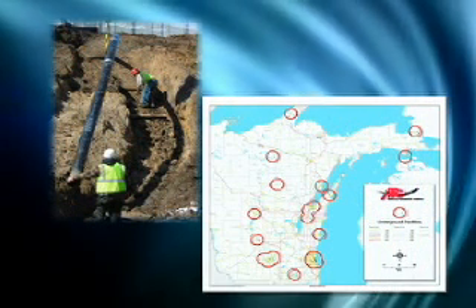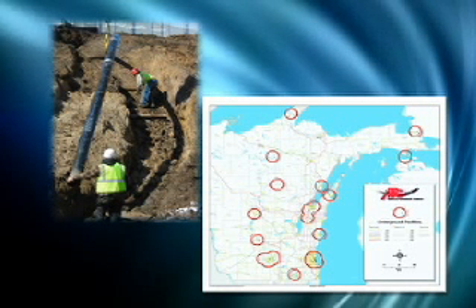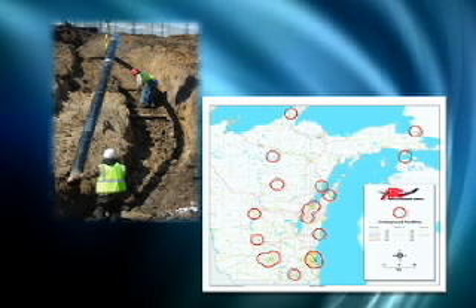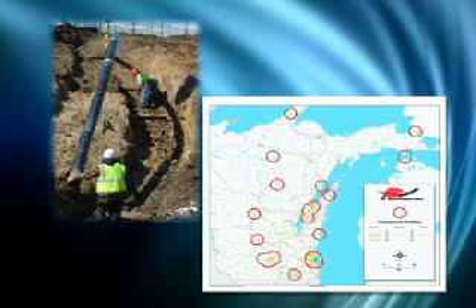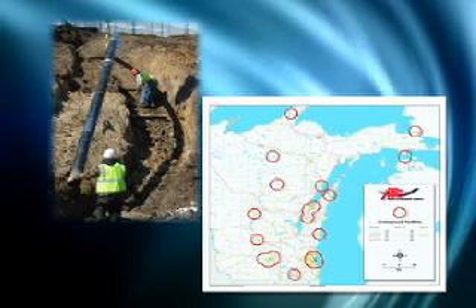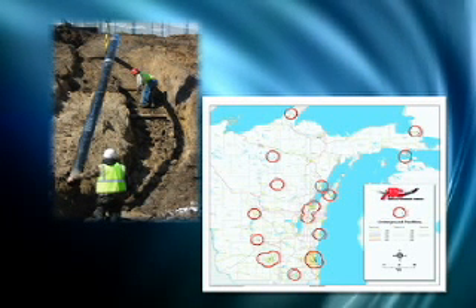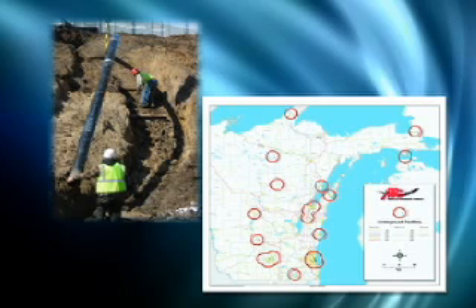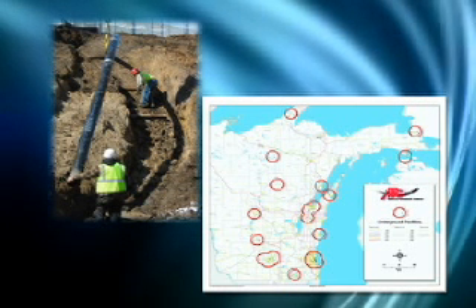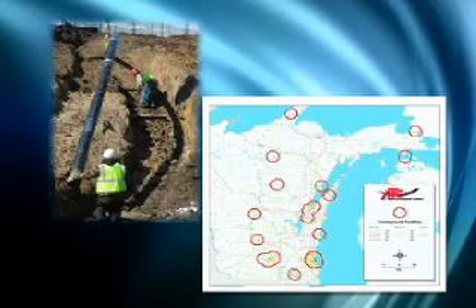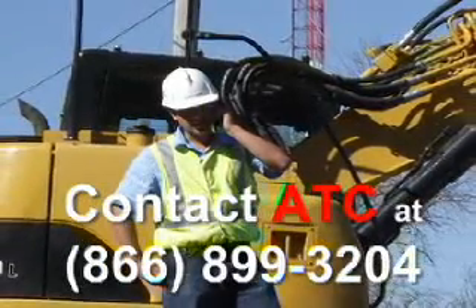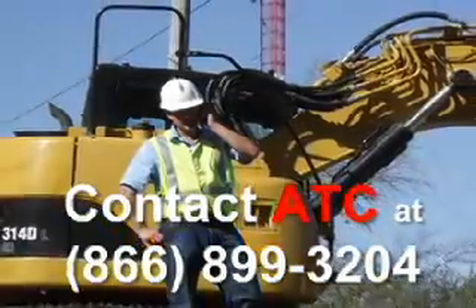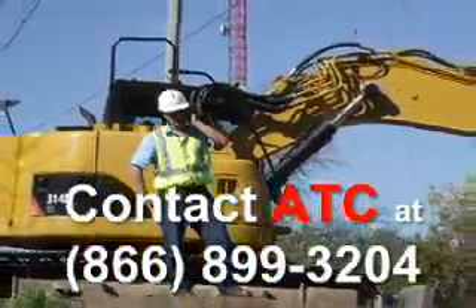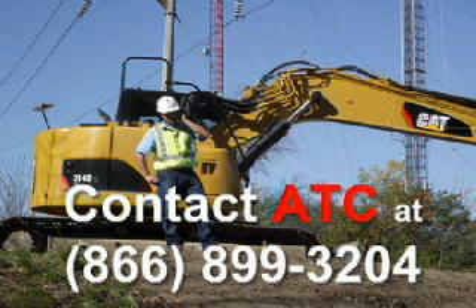ATC's underground high-voltage transmission lines are located throughout Wisconsin and Upper Michigan and can pose a significant danger to crews working around them if the proper safety measures aren't taken. Contractors are responsible for taking all necessary precautions to avoid damaging ATC underground transmission lines. The following will provide some guidance on working safely around ATC's transmission lines. All construction or excavation work done near ATC underground transmission lines must be supervised by an ATC representative. 3 days before engaging in any underground construction near ATC's underground transmission lines, contact ATC.